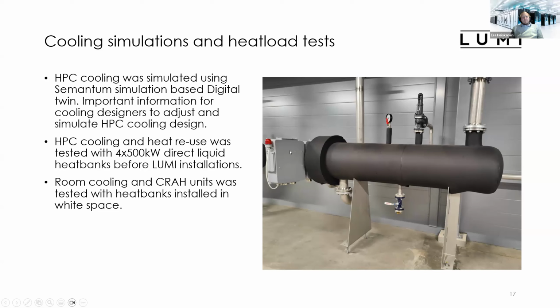HPC cooling and heat reuse were tested with 2 megawatt of total load directly with heat banks before the Lumi installation. We still have these heat banks in place, parallel with the Lumi cooling loop, which we could use to simulate 2 megawatt of IT load before the installation of the Lumi, when we had the data center construction ready and started the integrated system tests. Also room cooling and CRAH units in the data center white space were tested with the heat banks, which we installed inside the data center. So this gave us very important information about the cooling mechanism and how we need to adjust the cooling before the Lumi cabinets were installed.